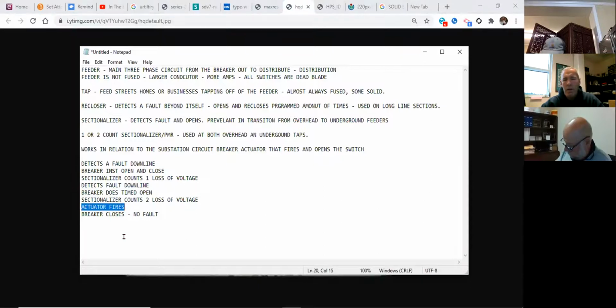Mm-hmm. So really, in the real world, a 2-count sectionalizer on a section of overhead or underground line is giving me 2 chances to clear the fault, and my breaker is set up for 3 operations. So I've given it 2 chances to clear a fault, but the breaker will close back and hold because the actuator had fired, and I haven't gone to my 3rd operation because the breaker closes, no fault. A lot of data going on there, isn't it? Realistically, this narrows down the field of hunting down where the fault is to just one small section where the actuator fires and opens the switch.